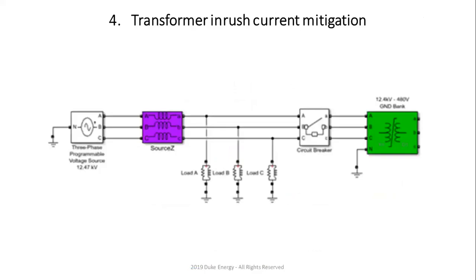Okay, probably the most challenging part: transformer inrush current mitigation. What are we doing? You saw what happens during the energization of the transformer: you have huge inrush current into the transformer if you close everything three-phase. And that is a function of the residual magnetism of the transformer and where you actually switch.